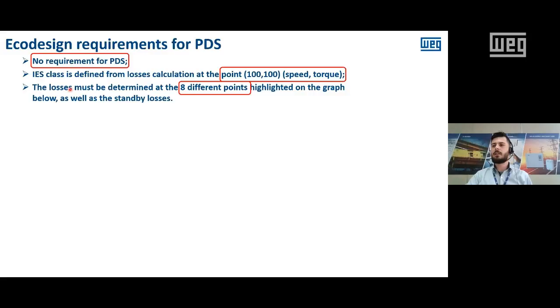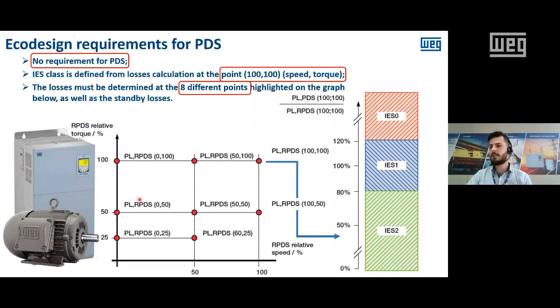So the losses here in the power drive system must also be determined at 8 different points, for the same reason as for the variable speed drives. And these 8 points are highlighted here in the graph. It's very similar to the variable speed drive. We have 8 points, but here the speed is going to be 100%. So the graph is for speed and torque.